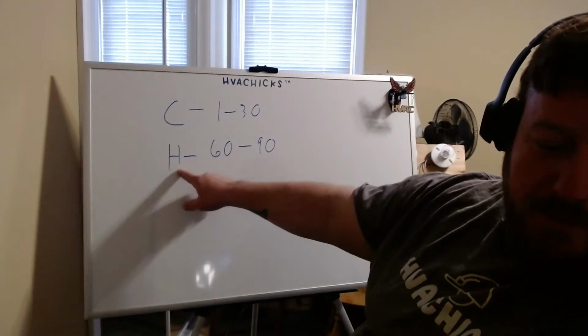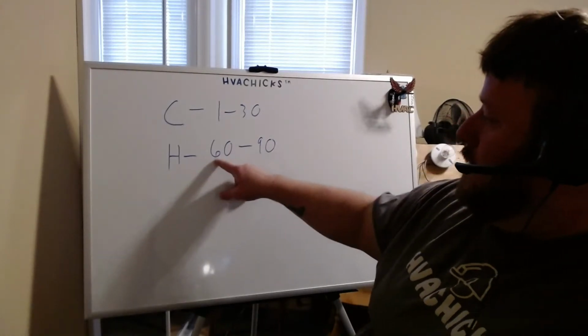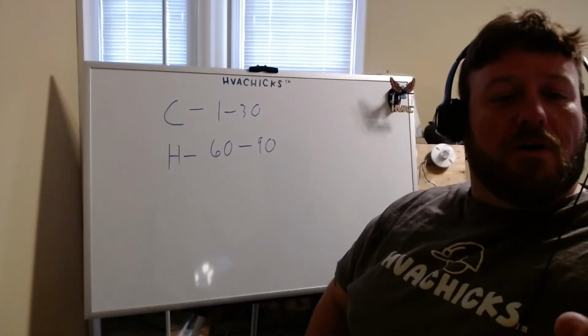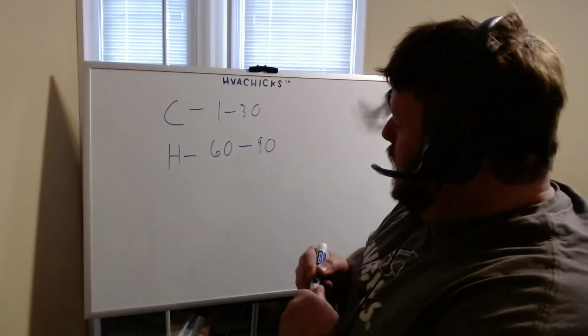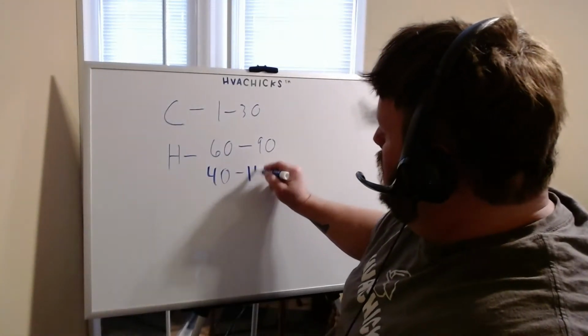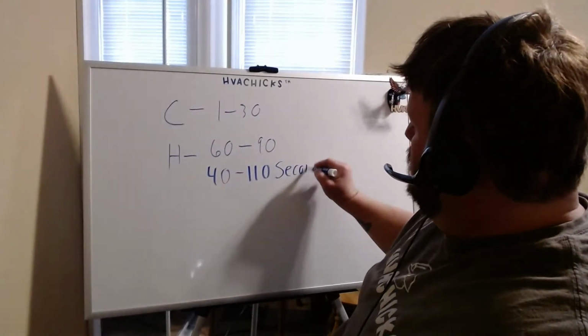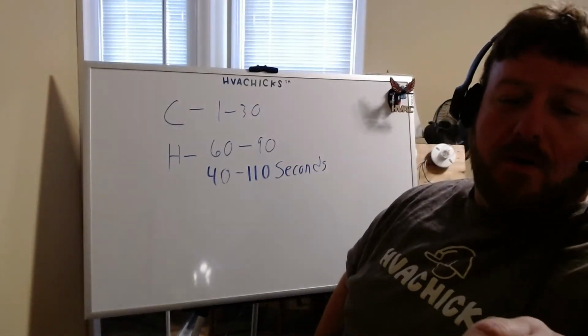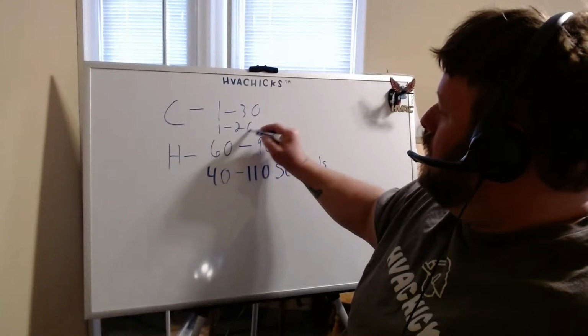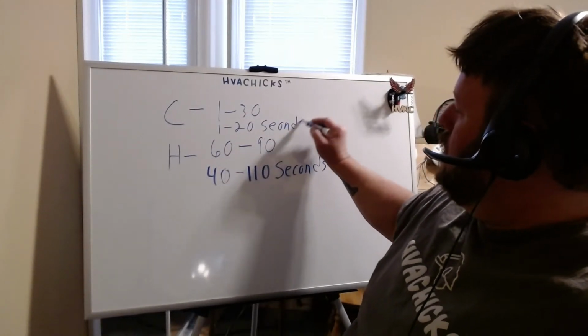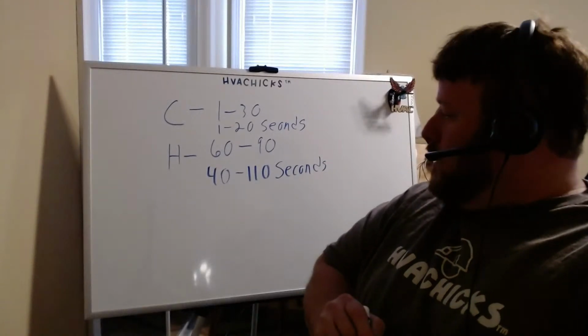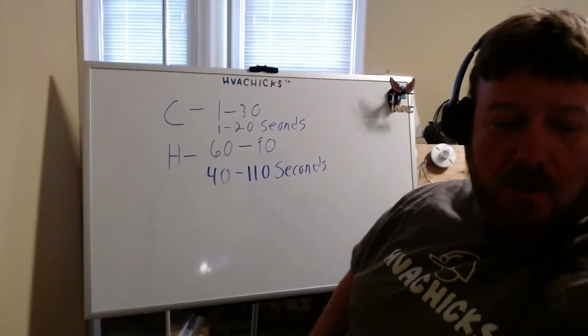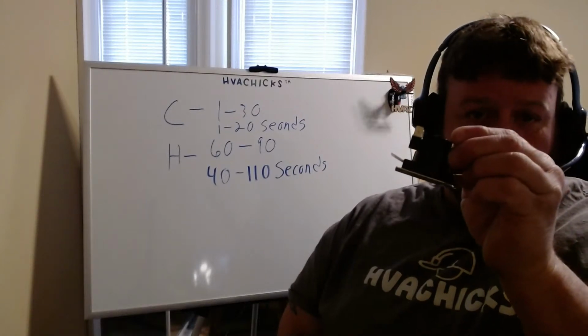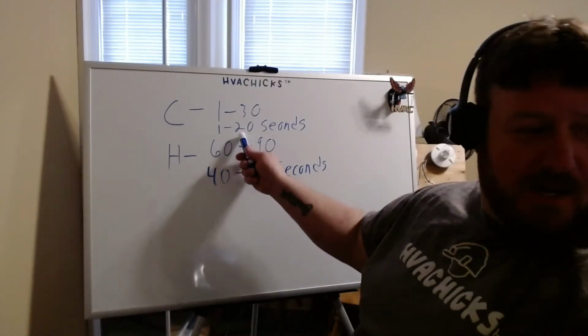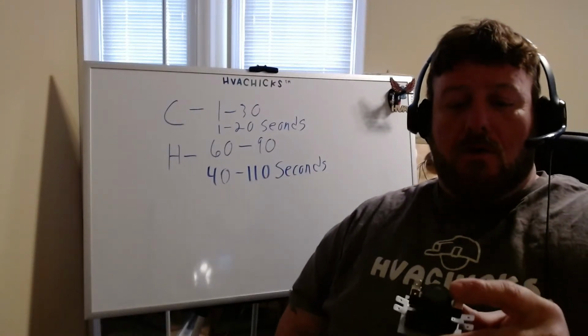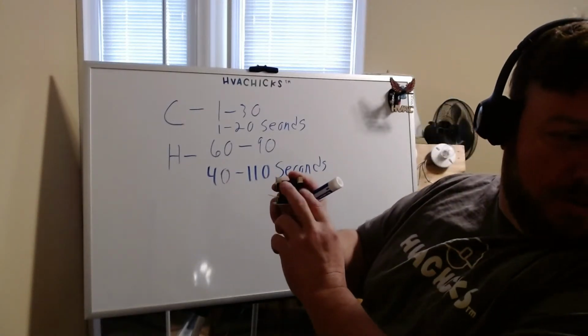So H stands for the heat up, how long it takes that bimetal disc to heat up. It could take 60 to 90 seconds. This one here says 40 to 110, so the one I have here is 40 to 110 seconds. On here it says 1 to 20 to cool down. So it could take 40 to almost 2 minutes for this to click on. It takes less time for it to cool down. And of course, they have M1, M2 on either side of it.